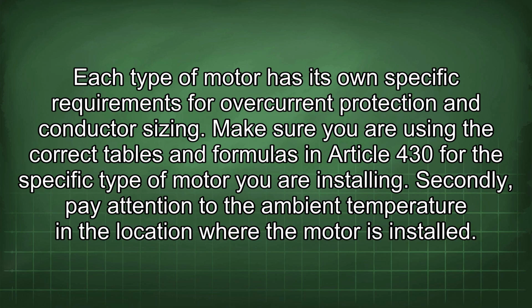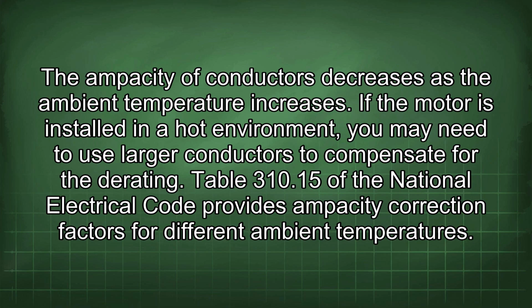Secondly, pay attention to the ambient temperature in the location where the motor is installed. The ampacity of conductors decreases as the ambient temperature increases. If the motor is installed in a hot environment, you may need to use larger conductors to compensate for the derating. Table 310.15 of the National Electrical Code provides ampacity correction factors for different ambient temperatures.